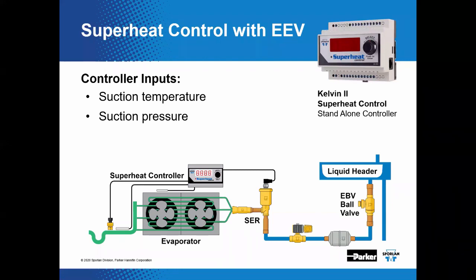Now, if this was a thermostatic expansion valve, how would all that be different, Glenn? Well, you'd have to correctly choose the valve to make sure you had the right power element with the right charge, and then you'd actually have to physically adjust the valve and observe what was happening with superheat to dial in superheat to where you need it. So that's where this commissioning process is expedited with the arrangement you see here with an EEV and the controller package. That is correct.